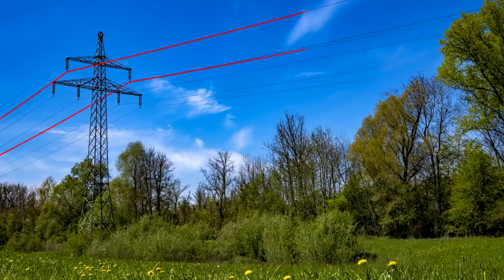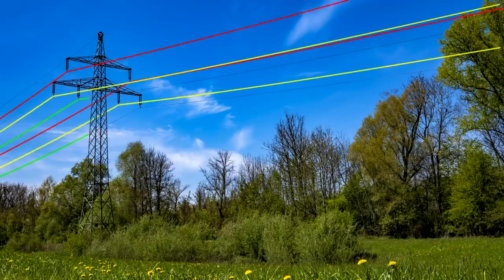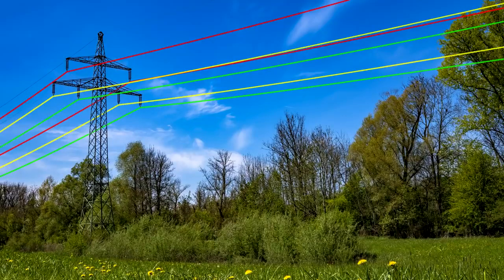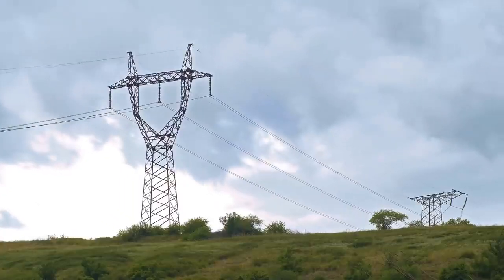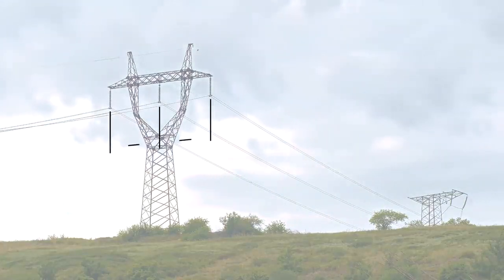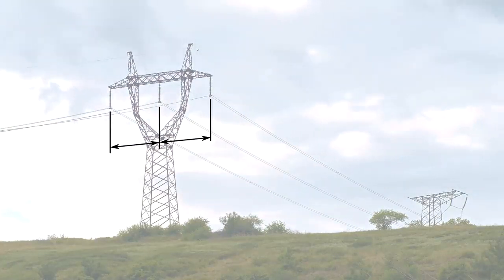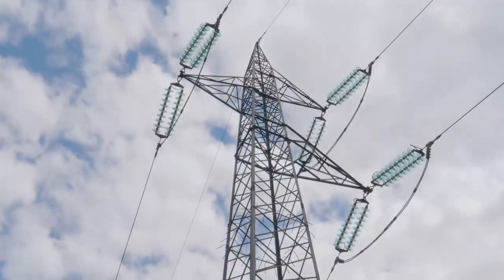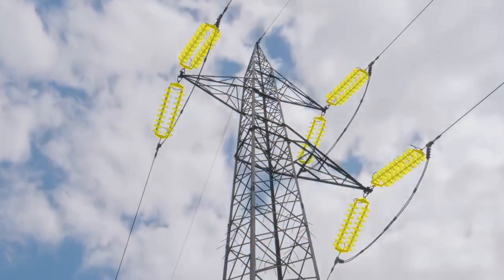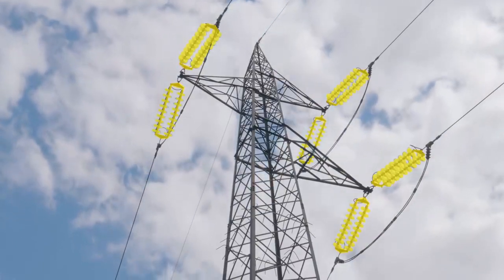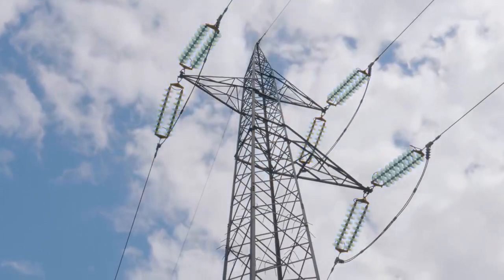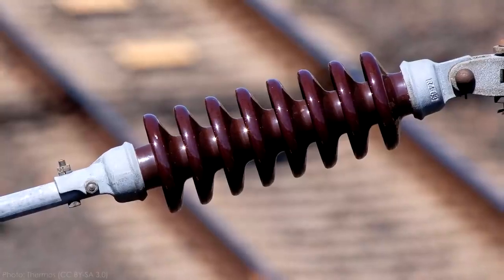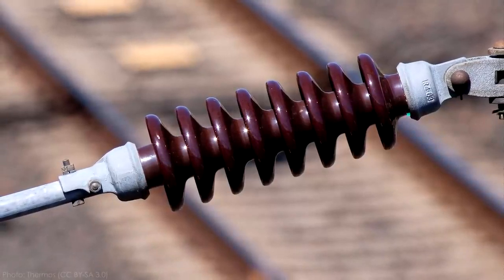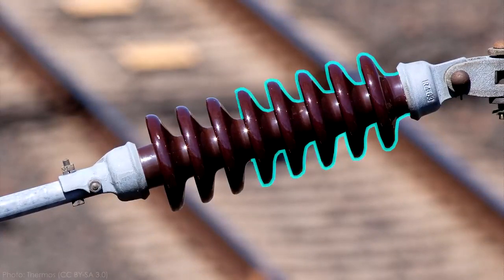Bulk electricity is transmitted in 3 phases, which is why you'll see most transmission conductors in groups of 3. Each phase is spaced far enough apart from the other 2 to avoid arcing between the phases. The conductors are connected to each tower through long insulators to keep enough distance between energized lines and grounded pylons. These insulators are normally made from ceramic discs so that if they get wet, electricity leakage has to take a much longer path to ground.